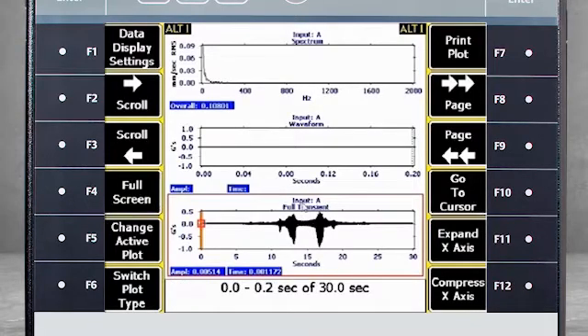What is the difference between full transient and waveform? Full transient is complete raw data. Notice the red box here on the far left. Using the scroll keys shown here, you can move the box right or left over the raw data. From the location of the orange box, you see the waveform displayed above and the spectrum calculated at the top.